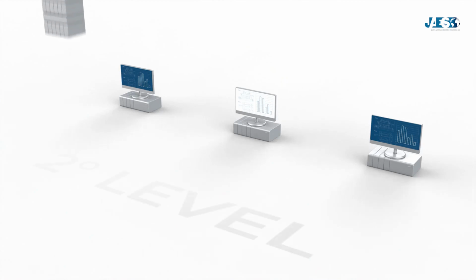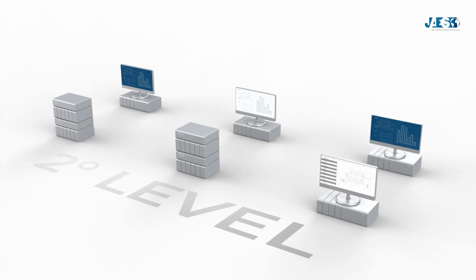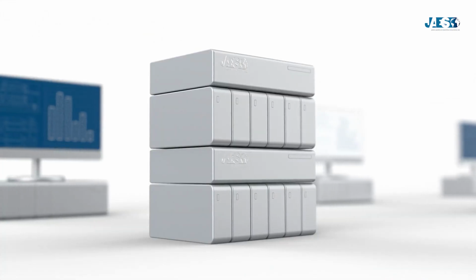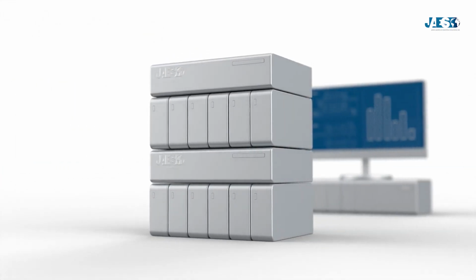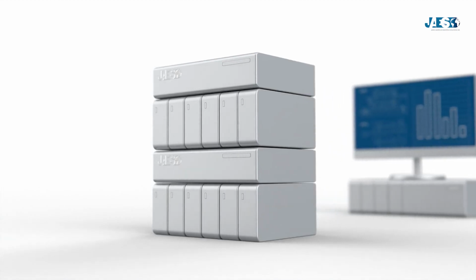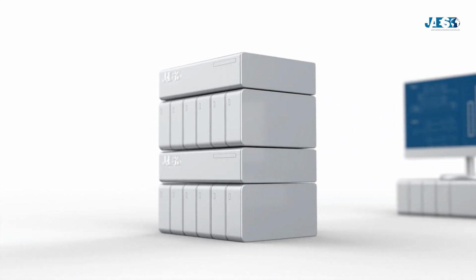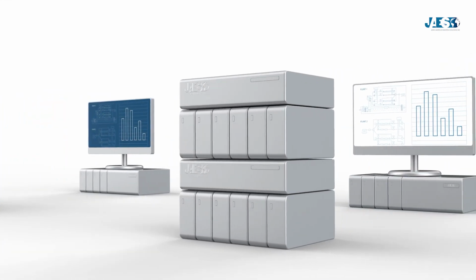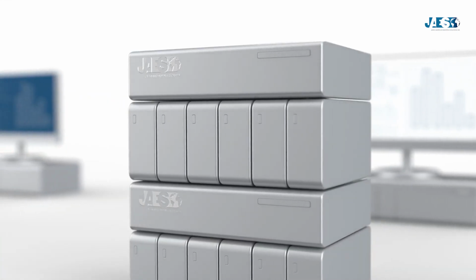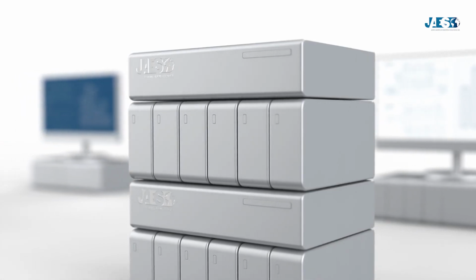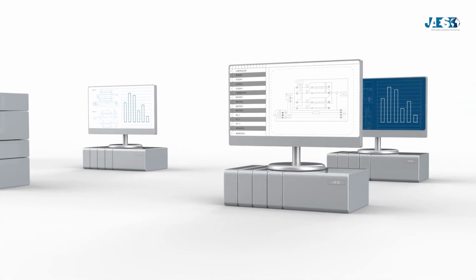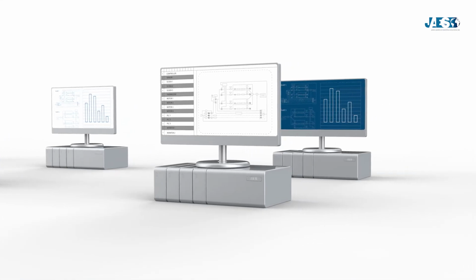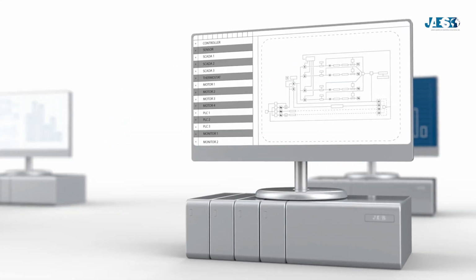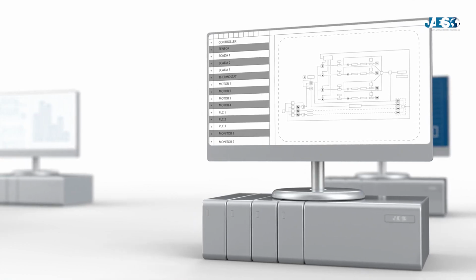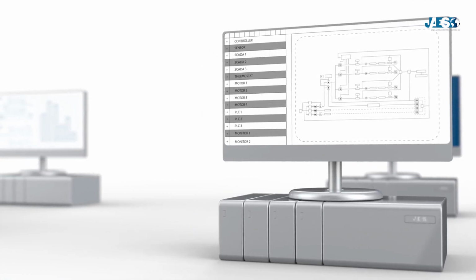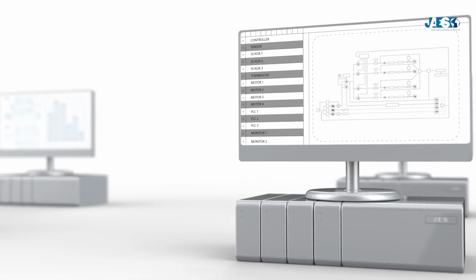In the next level, we find servers, storage computers, and design stations. The servers store the processor data and they are responsible for the communication between the computers of the control center and the plant processors. Storage computers are used to store historical plant data, such as projects and technical specifications. The design stations are used to create the projects on which the processes are performed, such as the hardware configurations and the graphics that the operator will see on the display. This is the station that will upload the projects to the various processors of the system.